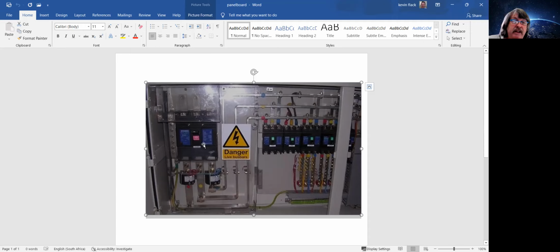So ideally, all the product on the load side of here should be rated to this breaker here. If this one was a 600, it would cause all the bus bars here to be 600 amp feeds out, fully rated at this breaker's rating. And if these were 250 amp, they would have to be bus bars like that going out to the load, or going out to a large cable connected.